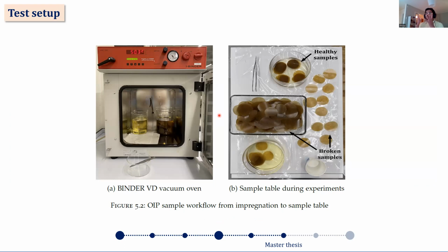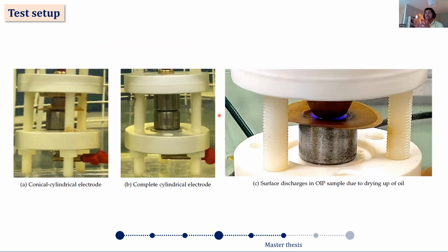OIP samples essentially stored in a vacuum oven. We would take out a bunch of them, immersed in oil still, for the tests, and then apply them one by one. The electrodes look something like this. There were 2 arrangements, a conical with a cylindrical, and both cylindrical, and we tested both of them for breakdown. I'll explain in the next slide. And here, when we didn't essentially dip them in oil, we can clearly see how there are some surface discharges when the oil started drying up.